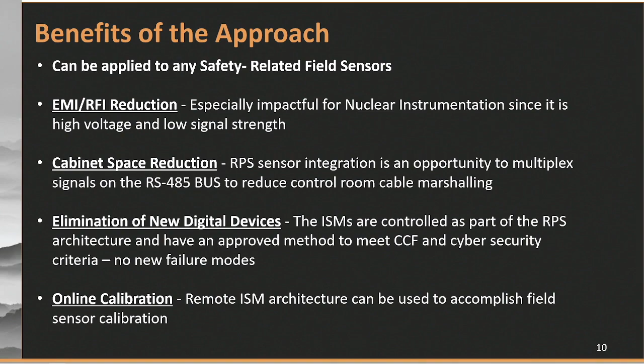We're also able to eliminate the need for new digital devices. As advanced reactors and small modular reactors look to suppliers for field sensors, a number of those sensors have their own digital components, which introduces new common cause failure evaluations, other digital failure evaluations, and cybersecurity vulnerabilities into the plant. If you can eliminate the need for those field sensors to have digital components and instead integrate them into the RPS as an analog signal, you can remove those challenges, taking advantage of the already licensed digital platform for a smoother transition into the reactor protection system.